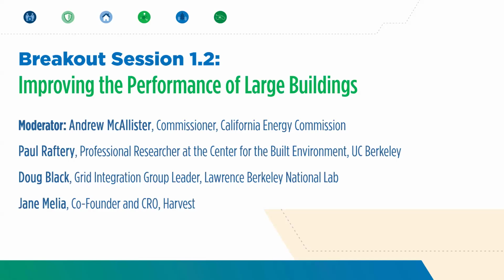There's other uses for hot water, like domestic hot water, that you could leverage at lower temperatures. But some of the latest innovations have heat pump equipment that can generate hot water at higher temperatures, like CO2 heat pumps, or some of these new screw chillers—really large heat recovery chillers. That makes them more directly applicable for retrofit applications, because you can service all of the building's heating loads throughout the year and make water hot enough to work in an existing building context. You take an efficiency hit, so you don't want to do it unless you have to, but if it allows you to feasibly electrify without replacing terminal equipment, it can really make the difference between a project working or not.